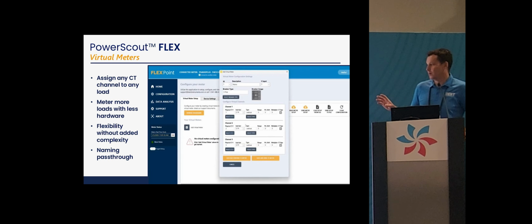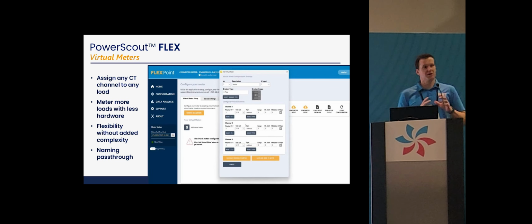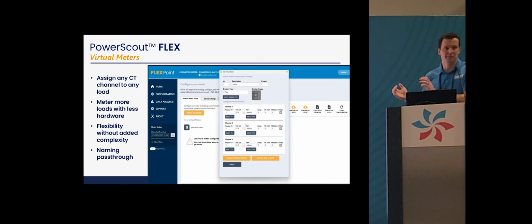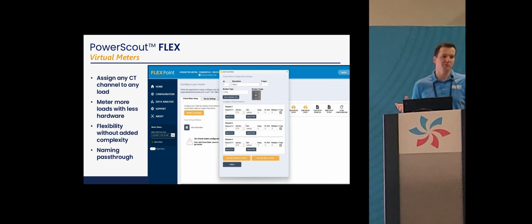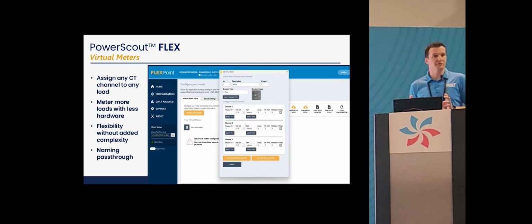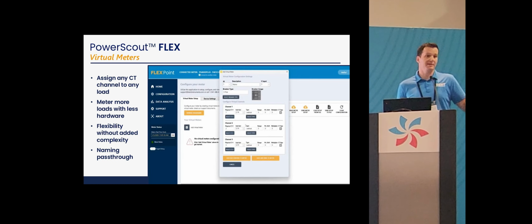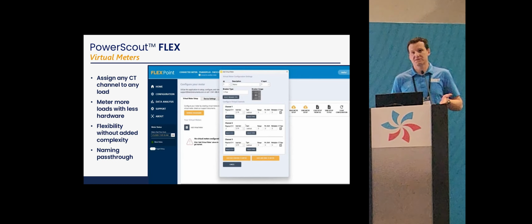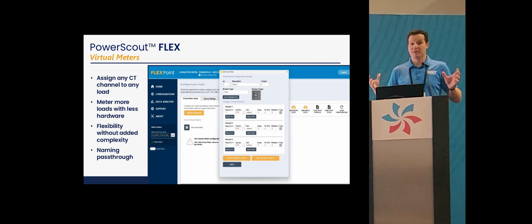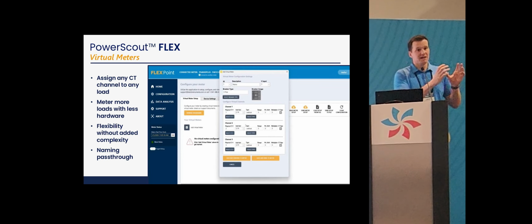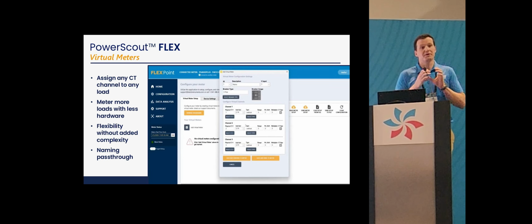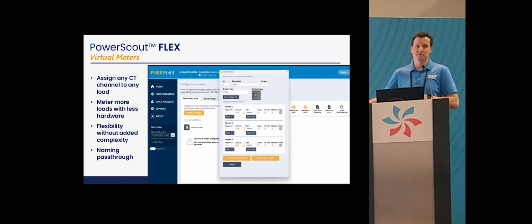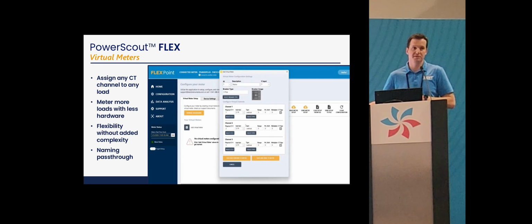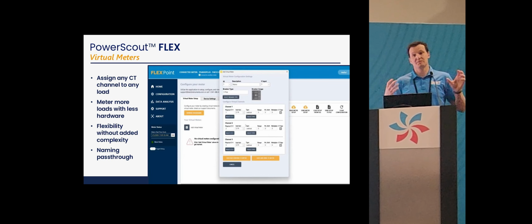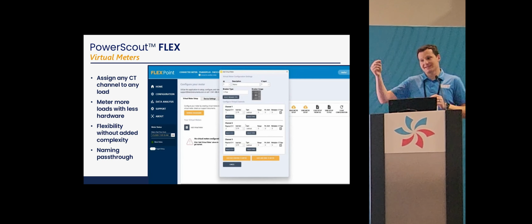Instead of having this architecture where everything is in groups of 3 phases, we've made it so you can do whatever you want. You can set up what we call a virtual meter, which could be a single phase load, a split phase load, or 3-phase load, and identify that as its own entity. You can name it, and it actually pushes through to your Modbus and BACnet registers.